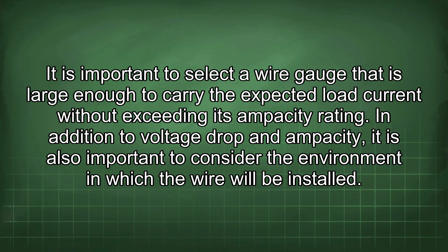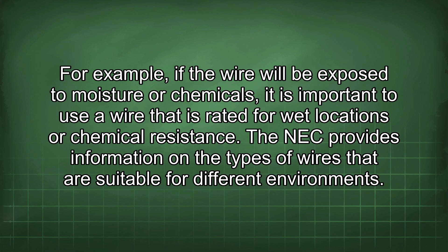In addition to voltage drop and ampacity, it is also important to consider the environment in which the wire will be installed. For example, if the wire will be exposed to moisture or chemicals, it is important to use a wire that is rated for wet locations or chemical resistance. The NEC provides information on the types of wires that are suitable for different environments.